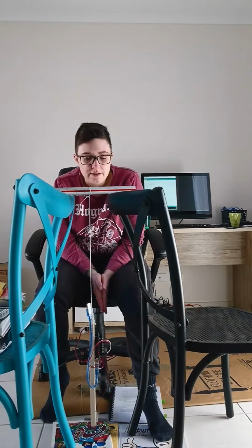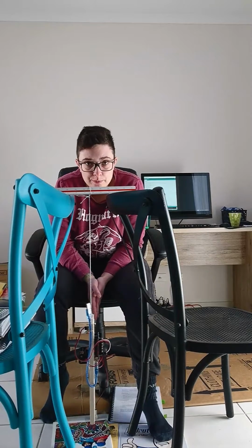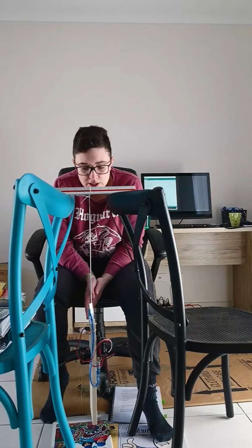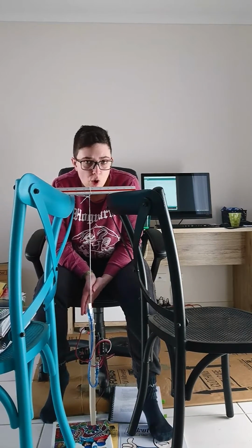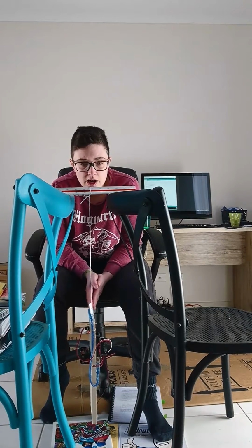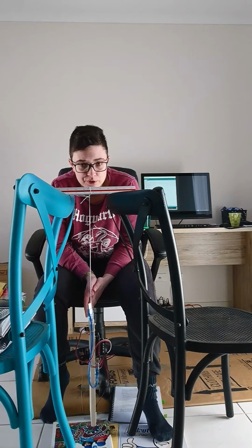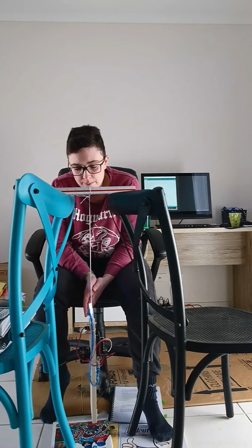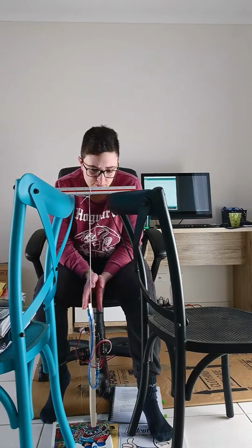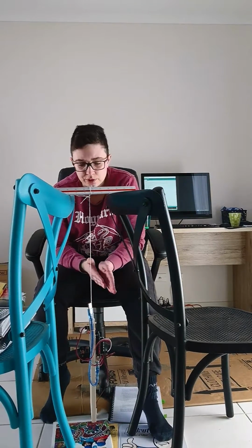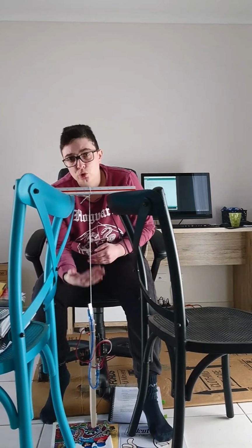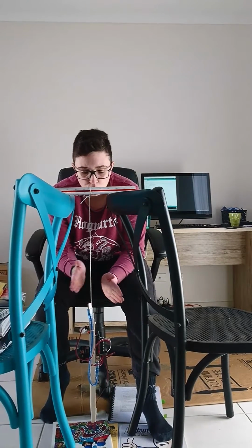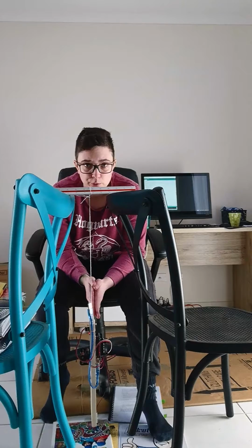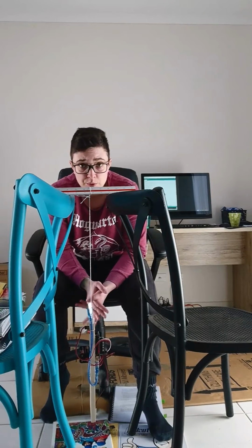I found that the small overshoot you observed, maybe 5 or 10 degrees, was an optimal choice for this design to ensure a responsive system. By increasing its rate of turning, it would help get it to its set point quicker, and that small overshoot is then very quickly removed, bringing it back into a stable position.